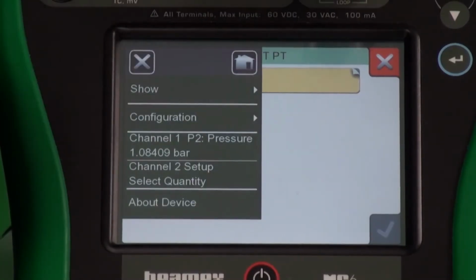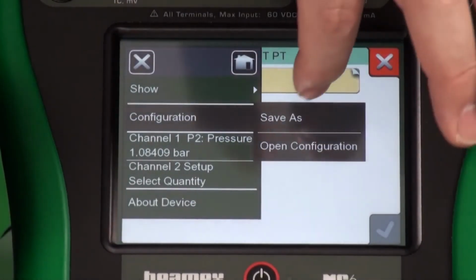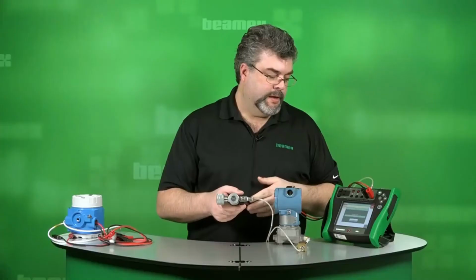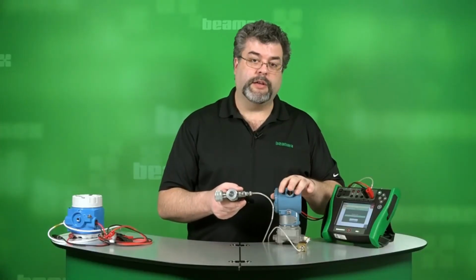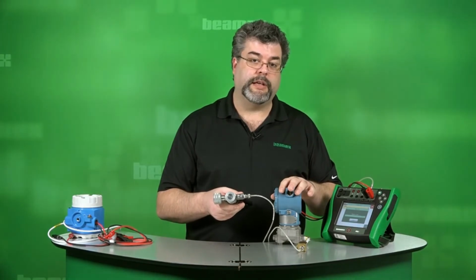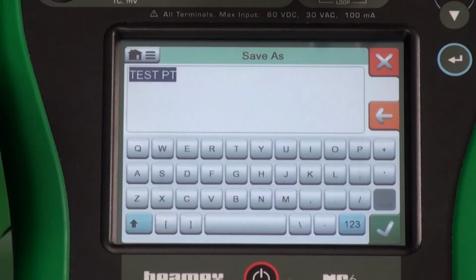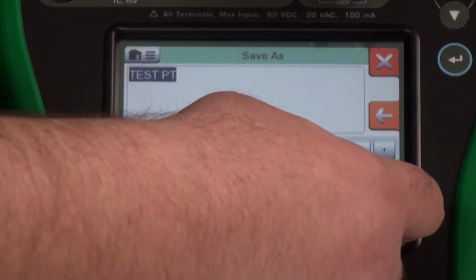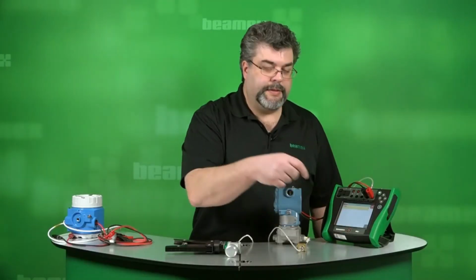That's through the menu button as well, configuration, and save as. So this will pull all of the HART information into a file which we can then name. Alright, that's done. Test PT will accept that as our name. Now that captures every variable inside the transmitter at its current state. You can upload this onto your computer for analysis as well or for documentation.